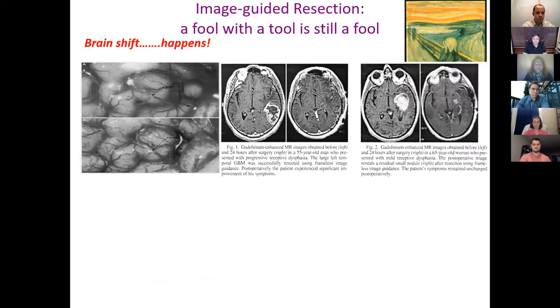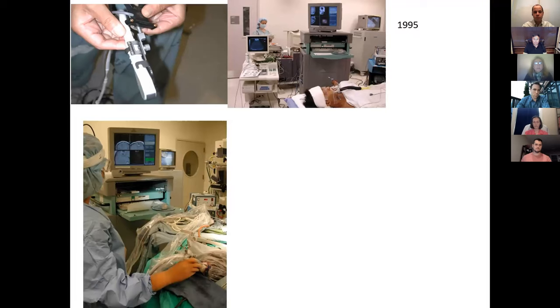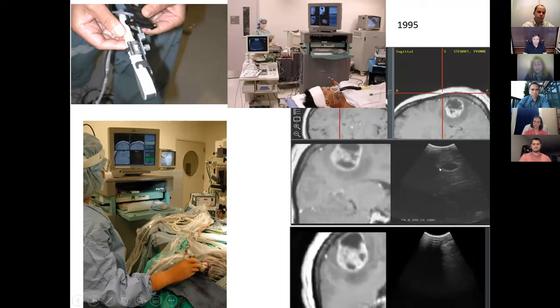Unfortunately, image-guided resection does not by itself guarantee gross total resection. We do know that brain shift can happen — this was published by one of our residents — and so some of those images have to be updated and upgraded. One possibility for metastatic disease is to use ultrasound. We developed this with what is now called Medtronic, where we can interface any ultrasound with the preoperative images. Intraoperatively, since all metastatic disease is echogenic, you can see it. At the end of surgery, you quickly scan the brain and see lack of echogenicity, which confirms a gross total resection.